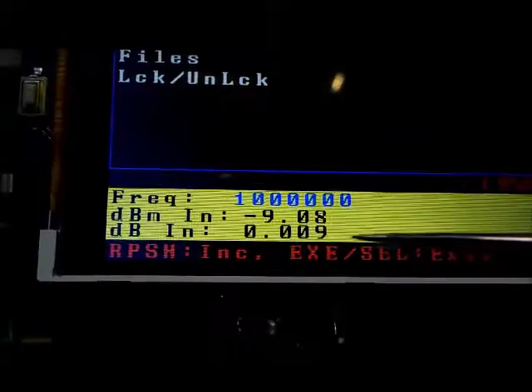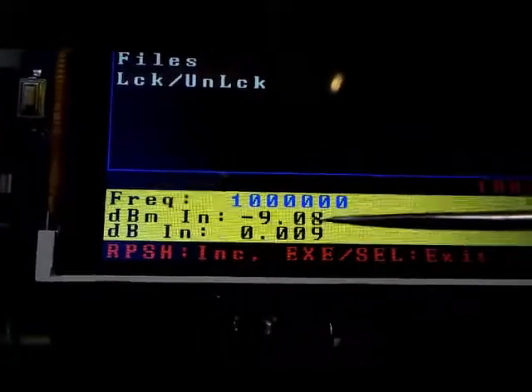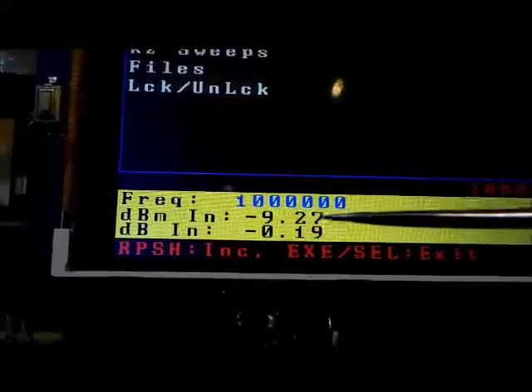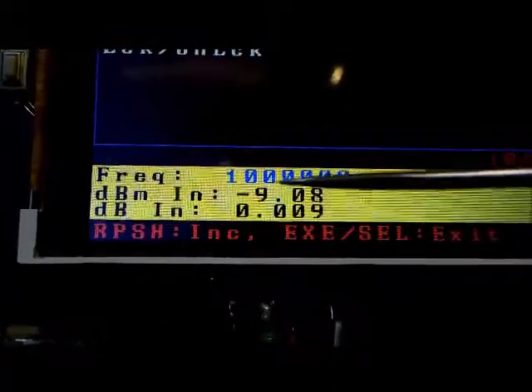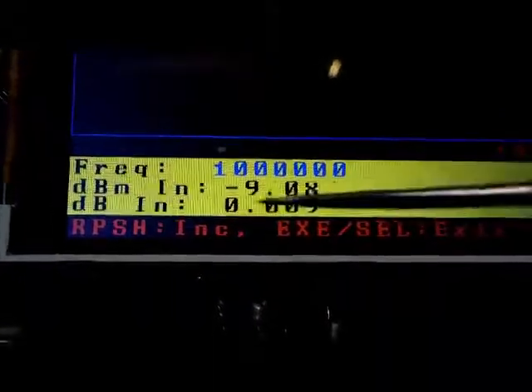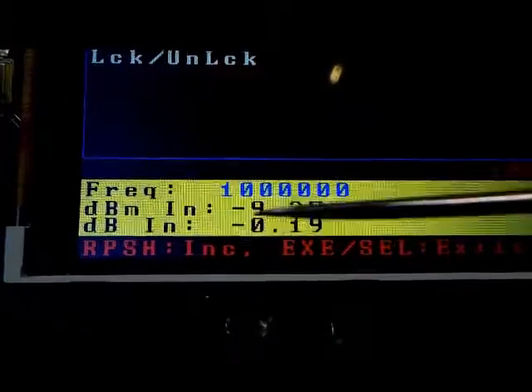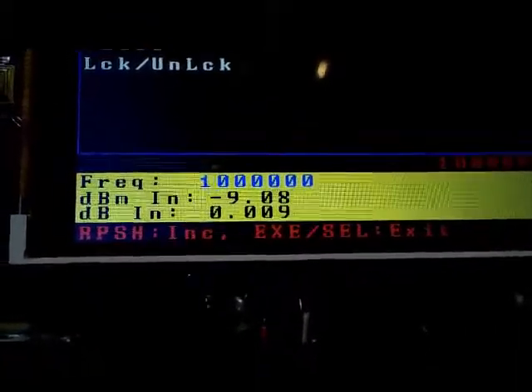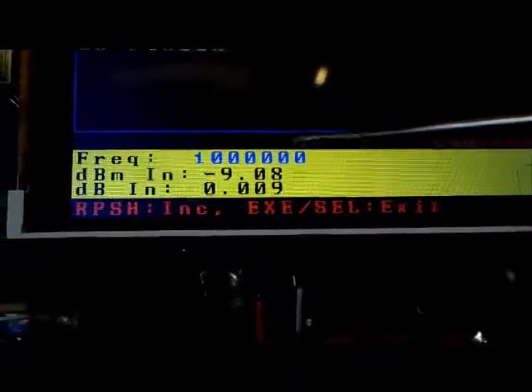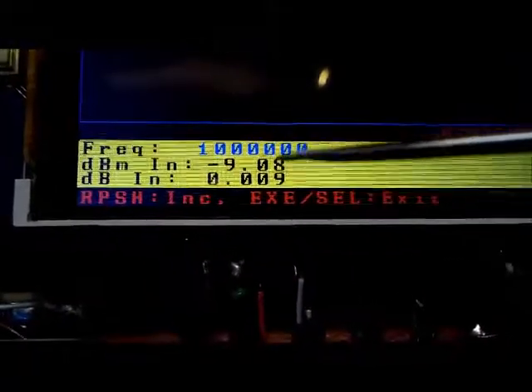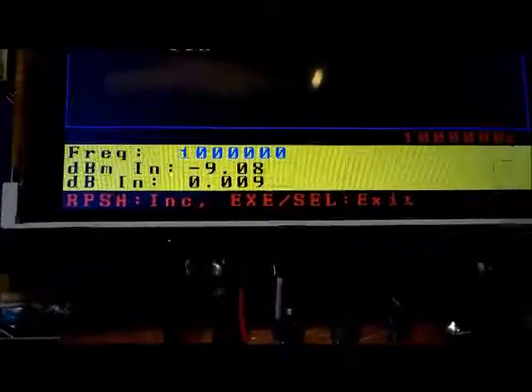The interesting thing to note here, because we've got it connected straight through, the dBm in is actually the dBm out of the signal generator. So right here, we're seeing about minus 9.2, say about minus 9 dBm. So that means that at this frequency, the 9850 is putting out approximately minus 9 dBm of power.